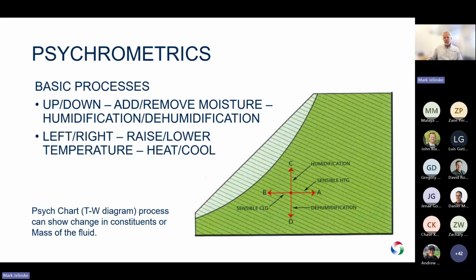HVAC processes can be represented on this chart. Humidification and dehumidification is represented by going up and down by vertical lines - remember, humidity ratio, absolute humidity, is on the y-axis, the right side of the chart. Going left-right on the chart represents a process of raising and lowering the temperature, heating and cooling. Both the vertical and horizontal lines are crossing the sloping lines, which represent other properties - wet bulb, and most important, the enthalpy. So for any one of these two points, A has more energy than B, C has more energy than D.